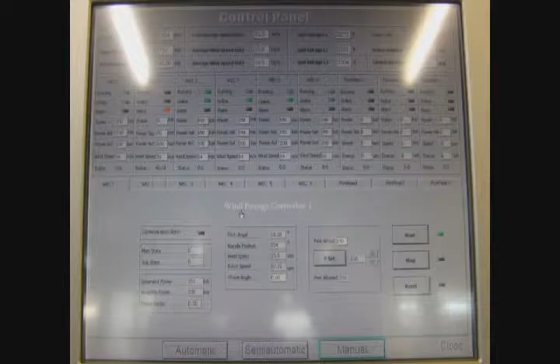What we've effectively done is sail below the wind. We look at our wind and ignore this bit—we set our turbines so that energy is just allowed to blow by. By not being completely greedy and trying to harness every single bit of wind, we've achieved penetrations which are, for me, still quite incredible. I used to read books on wind into diesel, and some would say penetration of 12%, 15%. Others would say with load banks and other things you could get to 20, 25%. But using our own concept of not grabbing every bit, by flatlining the output, we've achieved penetrations of 73%.